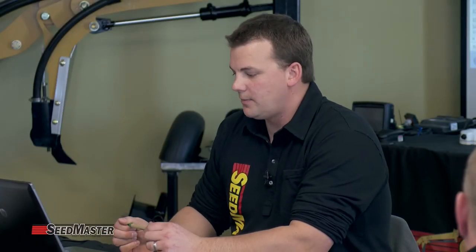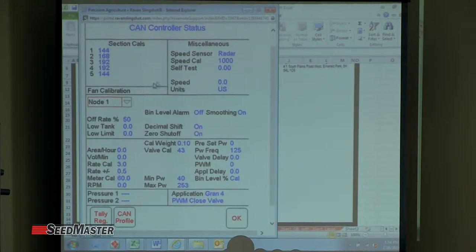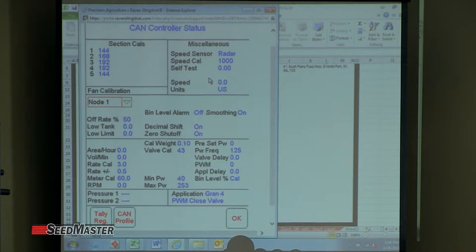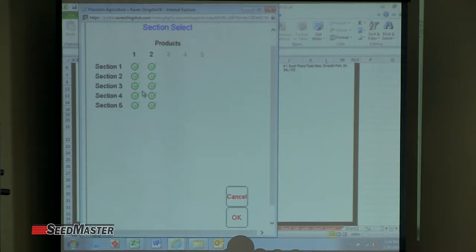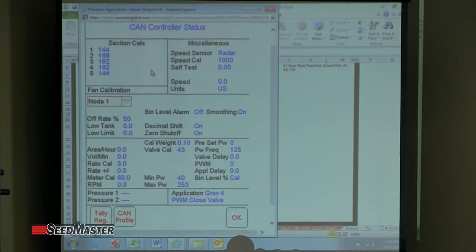We've been in and out of the product control page a couple times today. On page 93 of the manual, it explains each of the sections on the product control page. You've got your section cals, miscellaneous, fan calibration — all that. Each one of these boxes you can touch and it has different settings. These are all global settings on the Viper.